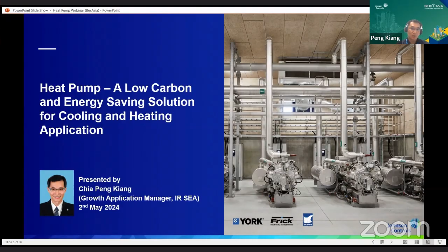A heat pump extracts energy from a waste heat source. From this waste heat source, we can go through a refrigeration cycle. Heat pumps work on a cycle very similar to any chiller cycle that you've come across. From the heat pump cycle, which goes to the compressors and condensers, some waste heat will be rejected to the condenser side, and from that rejection of heat we can extract it in the form of hot water.